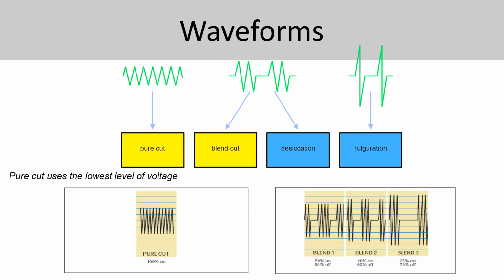So, waveform. When you talk about electrosurgical, you're going to see pure cut, blend, desiccation, and fulguration. Each of these modes has its own waveform. Pure cut uses low level voltage. Blend, the voltage will be higher. Desiccation and fulguration will be much higher. But the pure cut will be 100% on. When you press cut, the output will be on all the way. Blend, you're going to get 50% on, 50% off. You can see the frequency graph, that on and off sequence is there. Blend 2, 40% on, 60% off. And blend 3, like 25% on and 75% off.